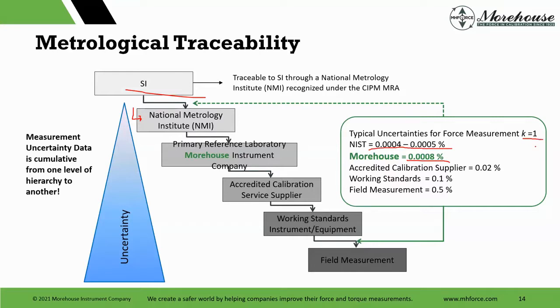Terms here being thrown around that everybody may not know what they mean. A standard uncertainty is before any coverage factors or anything else is applied to it. So we've reduced everything to K equals 1. Did that for a reason. Most people will operate, hey, I want whatever's 95% confidence. That's a different term too. That's a little bit more out of what we'll talk about today. If you're interested in that, we have other documentation that we'll talk about calculating uncertainties.